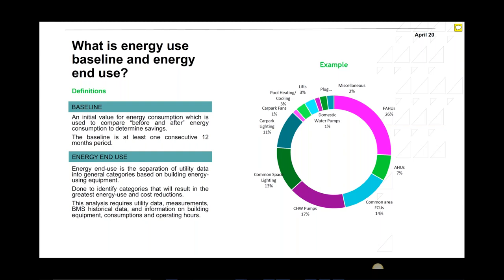Now, what is the energy end use? The energy end use is the separation of utility data into general categories based on building energy using equipment. It's done to identify categories that will result in the greatest energy use and cost reductions. This analysis requires utility data, measurements on site, BMS historical data, if you're lucky enough to find that working and they have been using trending on the BMS, and information on building equipment, consumptions, and operating hours. So you would rely a lot on what the facility management people will be telling you.